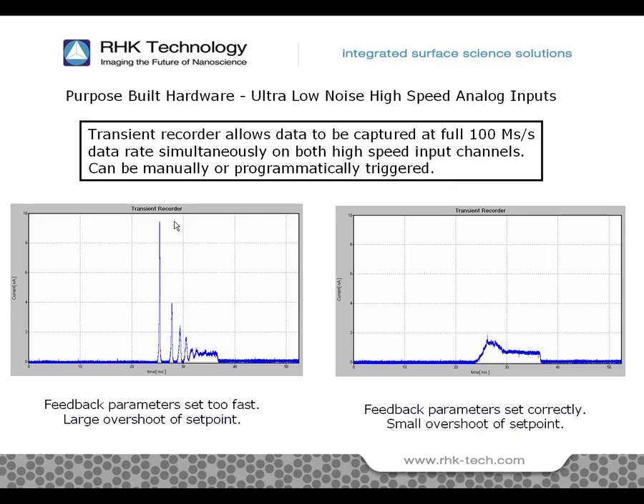One of the truly unique capabilities of the R9 is the ability to have such low noise and resolution while maintaining extremely wide bandwidth and timing resolution. Our transient recorder, which runs in parallel to our low noise data pathway, allows high-speed information to be measured with up to 10 nanoseconds precision.